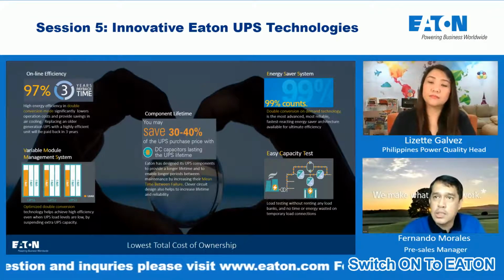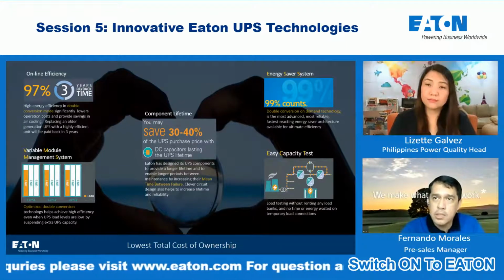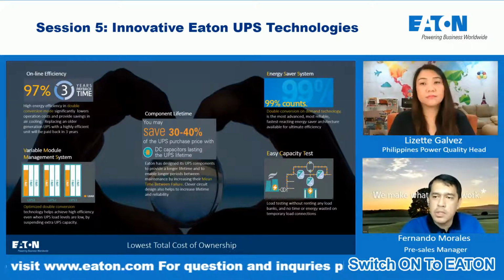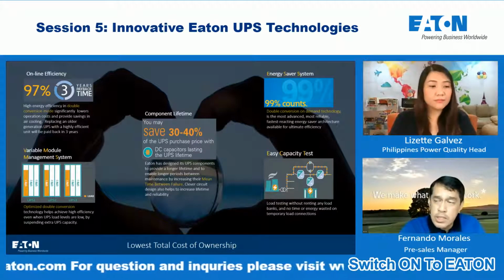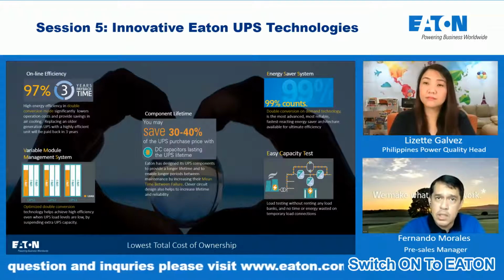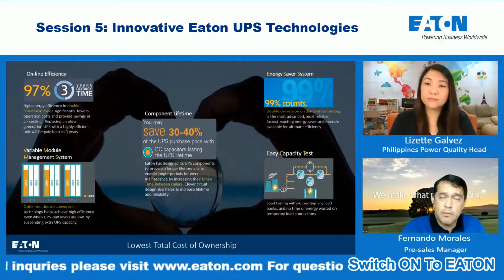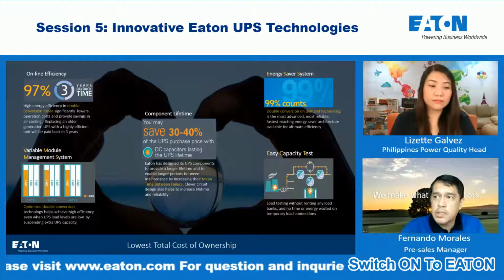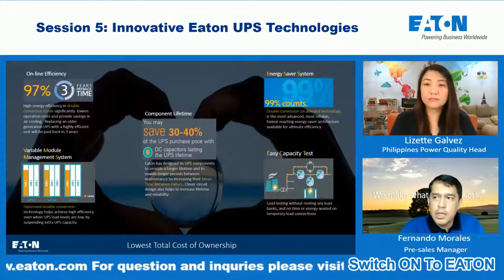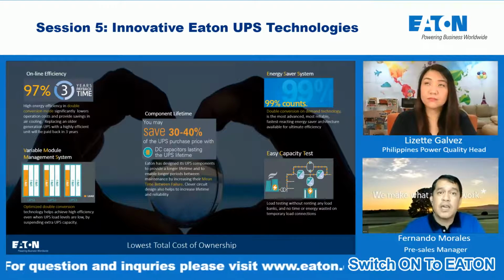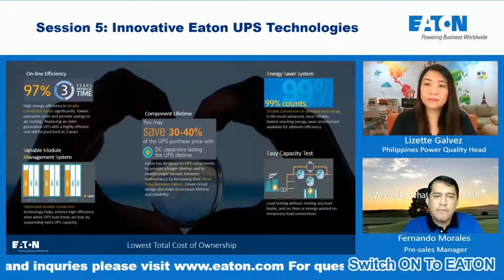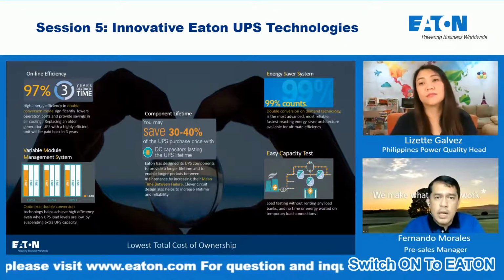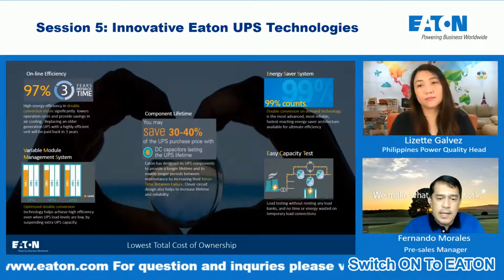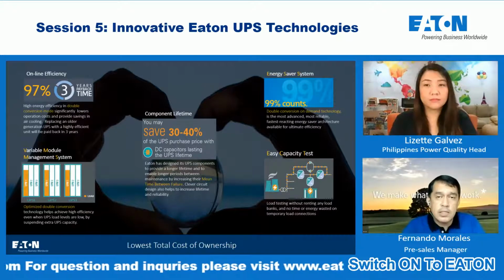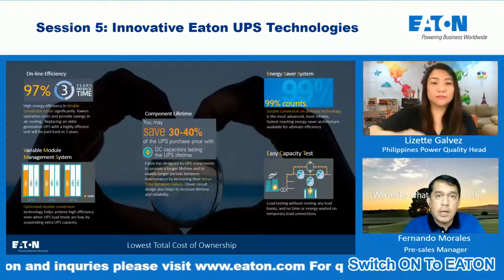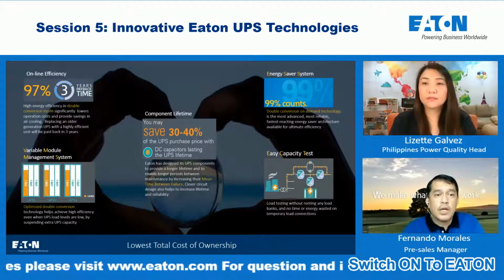All in all, if we sum up these features of our UPS: the online efficiency; if they have a modular UPS, they can use our VMMS; and then they can use Easy Capacity Test for their annual preventive maintenance, which can reduce maintenance cost if they require full load testing annually. And of course, with the design of our components, replacing, for example, the DC capacitor will last the lifetime of the UPS. So this is one way we help our customer not only enjoy very good uptime in their critical systems, but at the same time enjoy savings in the operational cost of their UPS systems.